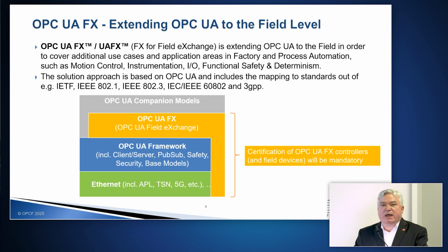So far, OPC UA has a voluntary certification, but because OPC UA FX is dealing with critical operations in machines, in skids, it was clear we have to get the certification done, and this is why anyone that wants to promote now a controller or later a device with OPC UA FX has to undergo certification. For this we have a program in place, we have a testing tool in place, so it should hopefully not be too complicated to get vendors through this process.